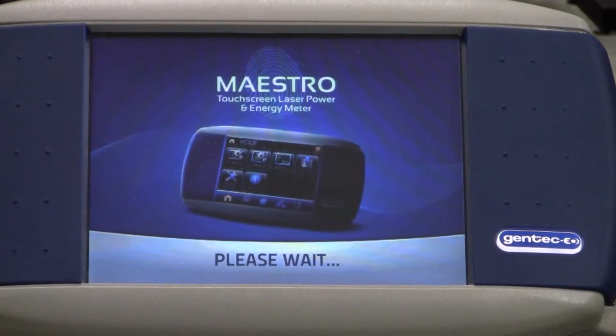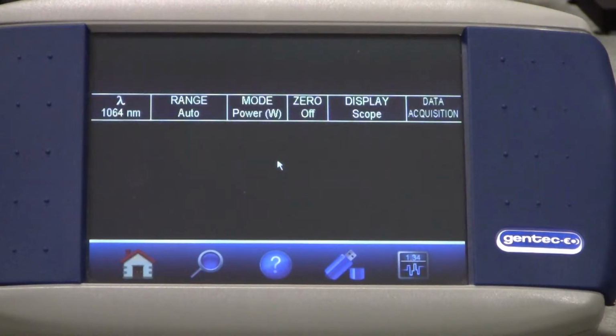It will take about 10 seconds to come on as MAESTRO reads the probe E2 prom to identify the probe and access the calibration and wavelength correction data. The instrument comes up in the auto range mode and begins to search for the appropriate power range, and once found begins to measure power.